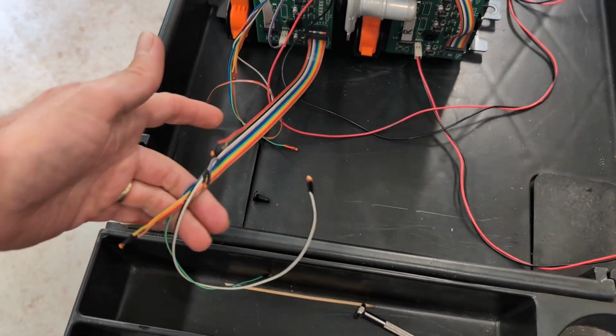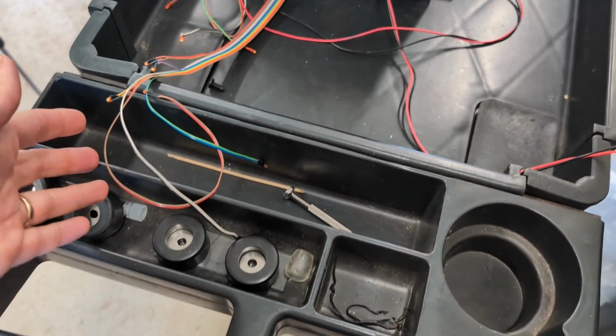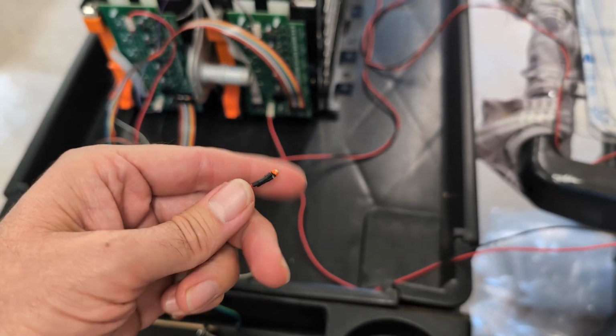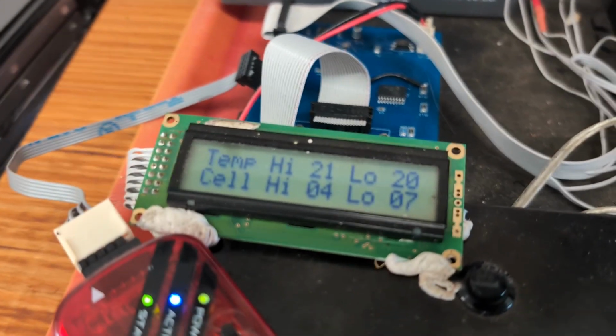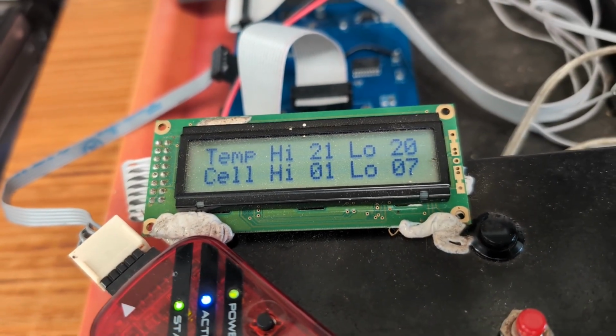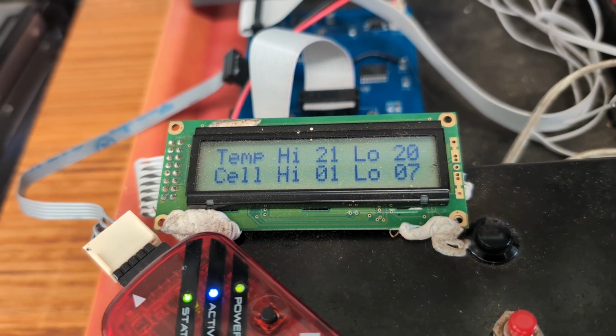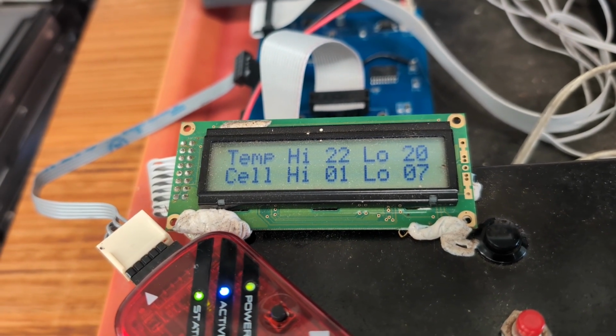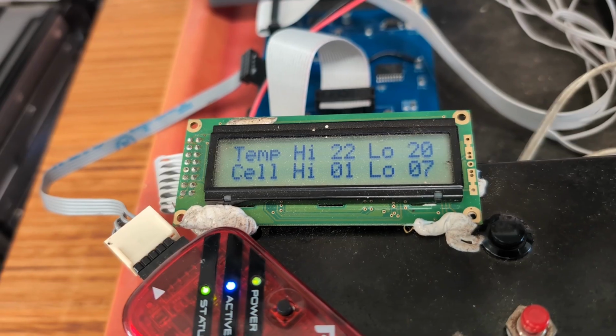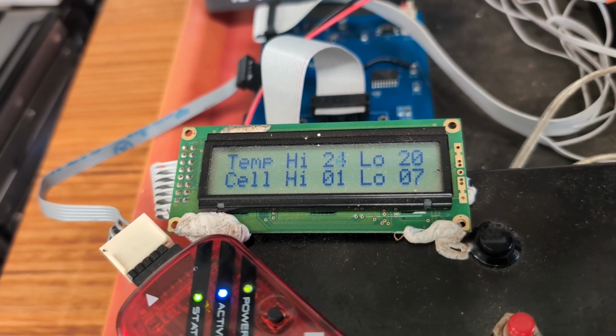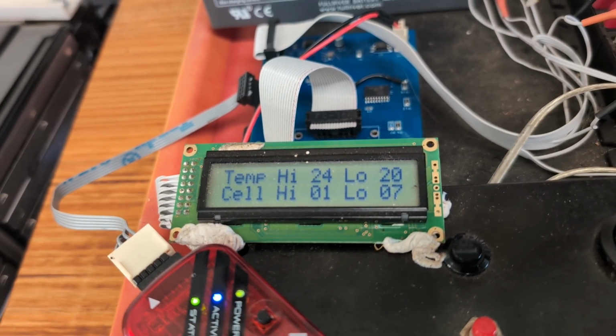What I like to do is I go through and check each one of these. So here, this one should be number 1. What I'll do is I'll put my finger on that and then we'll watch what it does here. So what we're looking for is the highest temperature should go up and it should become number 1. Yeah, it's just going to become number 1 anyway, just by hanging onto the wires. If I put my finger on the sensor, it quickly goes up a degree or 2.